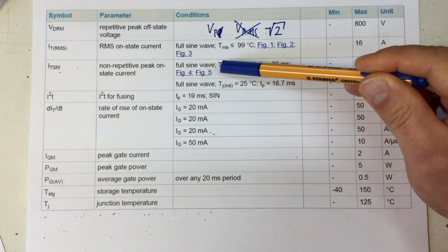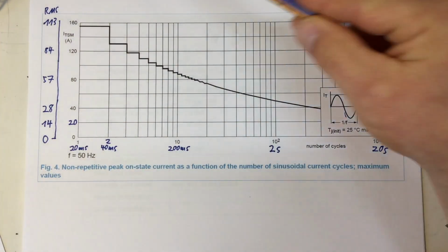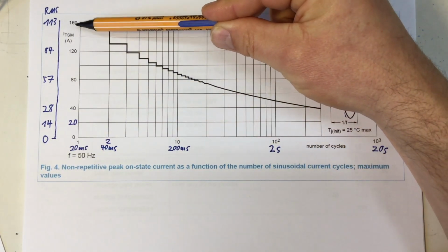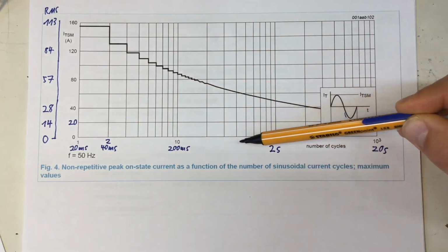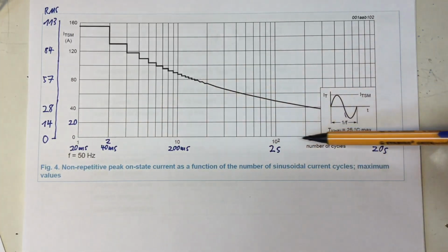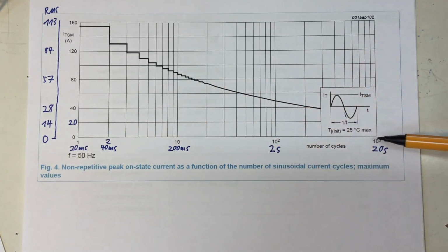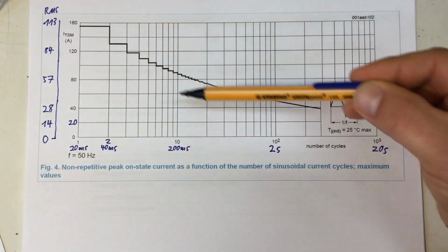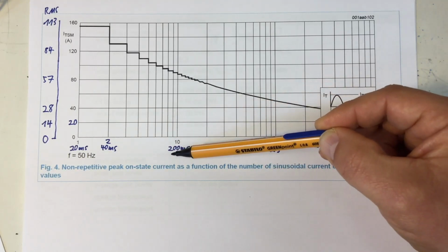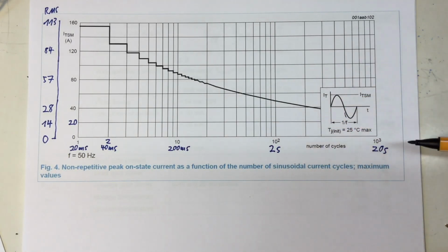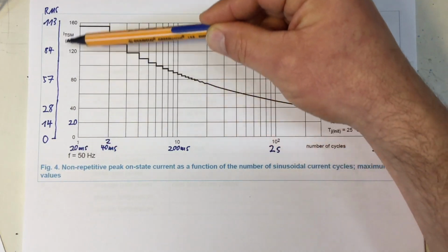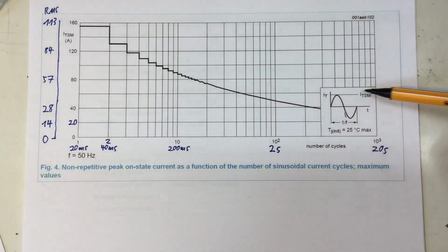And of course, we have some figures. The first graphic shows you how much peak current you are allowed to pass through the terminals in relation to how many cycles you intend to do that. I mean, the number of cycles at 50 Hertz, you can translate that easily into time. So one cycle is 20 milliseconds, two cycles 40, 10 cycles 200 milliseconds, 100 cycles 2 seconds, and 1000 cycles 20 seconds. And you can translate the peak current of the sine wave, of course, into an RMS current.